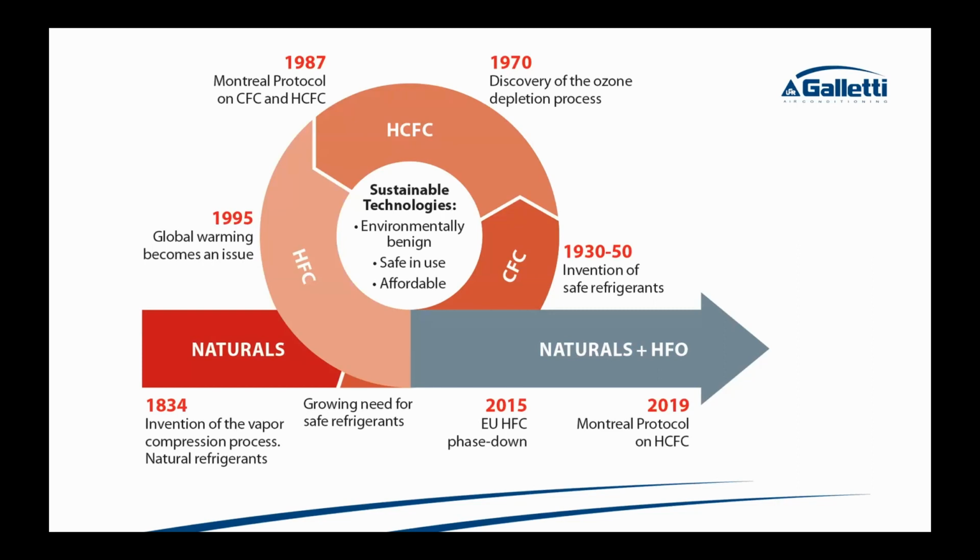And if I had to put a bet on it, I'd say in the next 2 years, we'll have progress here in the States where a lot of these things will be lifted. But earlier when I mentioned ASHRAE 15, which creates the standards for the safe handling of refrigerants, right now, the standard 15.2, there is an addendum E that went out at the last winter ASHRAE conference.